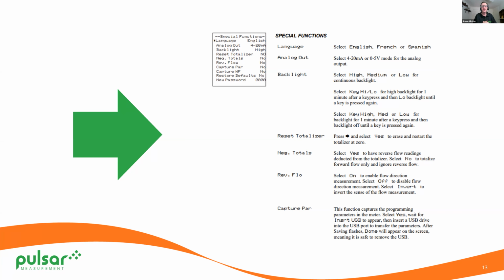go into special functions, record that information, and send us the file. I'd say 8 times out of 10, just by looking at that waveform or parameter form, we can tell you, hey, it's our fault, there's an equipment issue, or you know what, this particular area where you have this set up may not be the best spot. Maybe we need to try a couple of other things. That's revolutionary for us because it used to take sometimes weeks to get those units back into the hands of the people after we checked them out. Now it can take less than a day, depending on when you reach out to us. So that's a really cool feature.